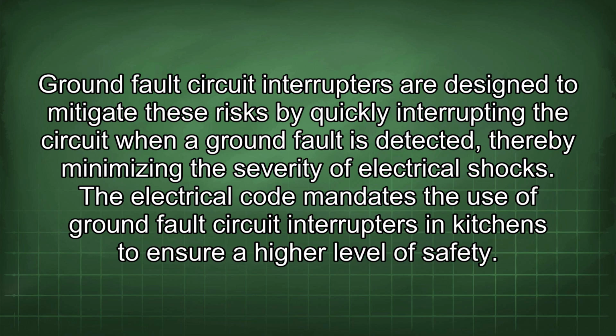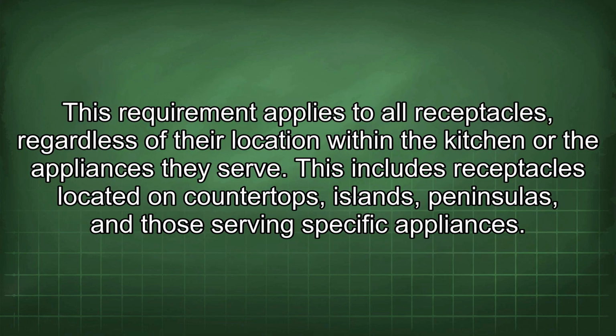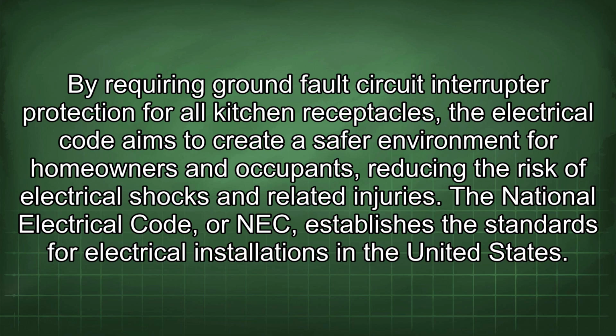The electrical code mandates the use of ground fault circuit interrupters in kitchens to ensure a high level of safety. This requirement applies to all receptacles, regardless of their location within the kitchen or the appliances they serve. This includes receptacles located on countertops, islands, peninsulas, and those serving specific appliances. By requiring ground fault circuit interrupter protection for all kitchen receptacles, the electrical code aims to create a safer environment for homeowners and occupants, reducing the risk of electrical shocks and related injuries.